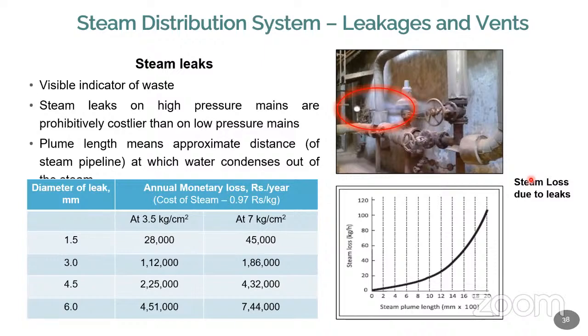There is no separate meter available. Of course, recently one company came out with a sonic analyzer. They use this sonic analyzer to find out the steam leakage, but visually we can also find out the leakage. Now you can see the leakage size and the pipe size. We have a 1.5 mm small hole in the pipe.